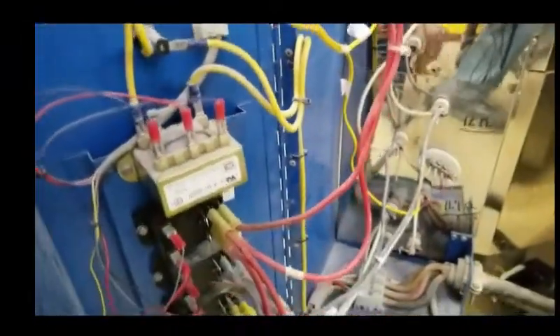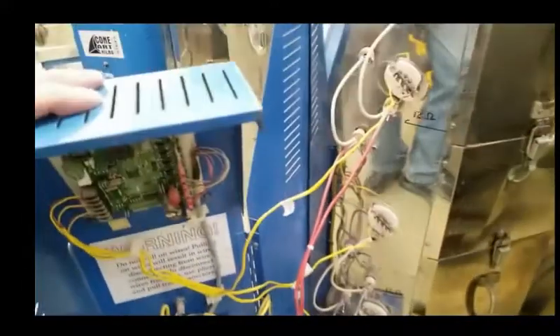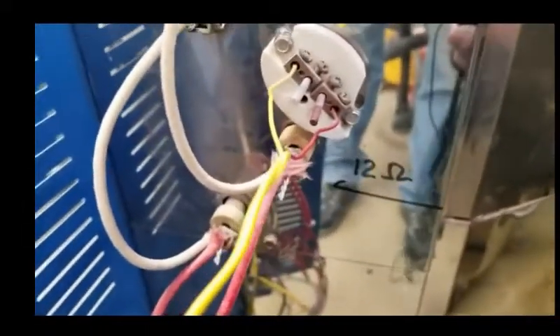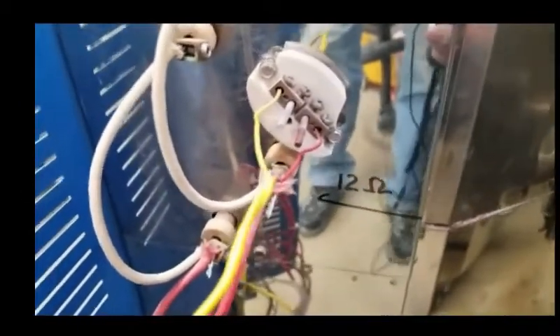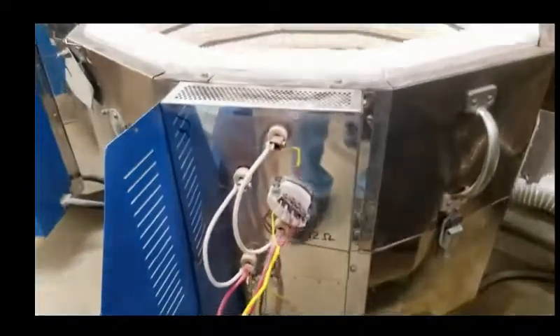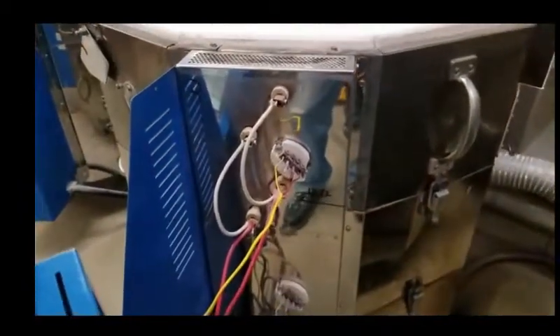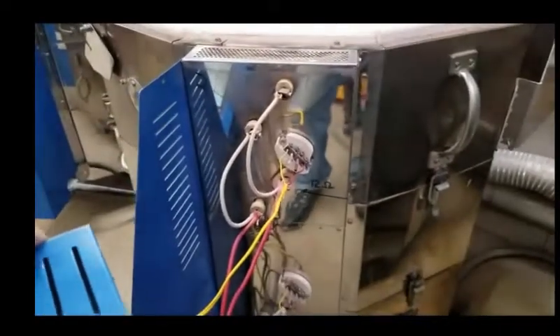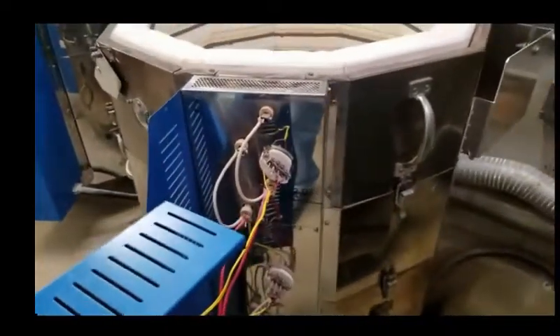So everything looks in good order from a visual exam. Now what we're going to do is set up. If you can see on the mark, I've marked 12 ohms—most kiln manufacturers will tell you the resistance rating of their elements. So if you have that, that's 12 ohms, and that's 11.7. Next we're going to set up and measure the resistance of these. Stand by and we'll do that in a minute.